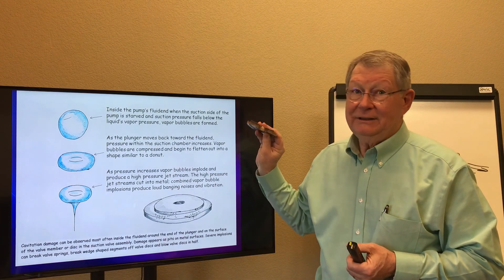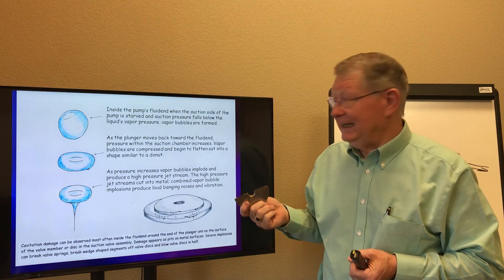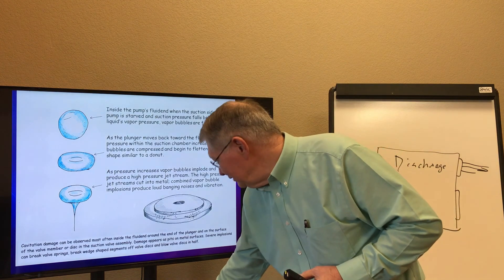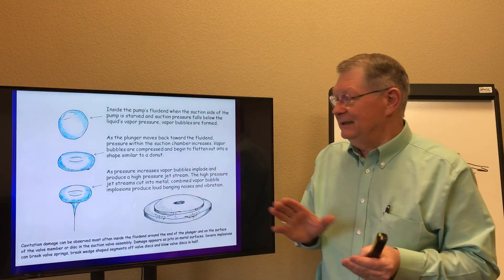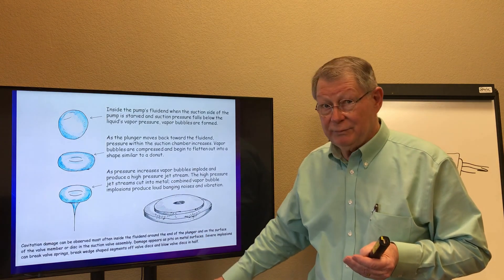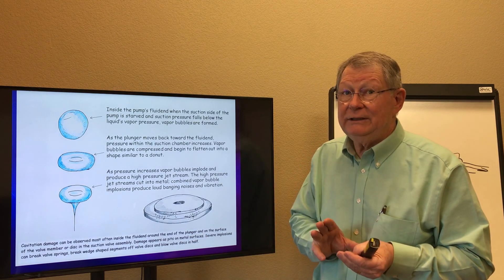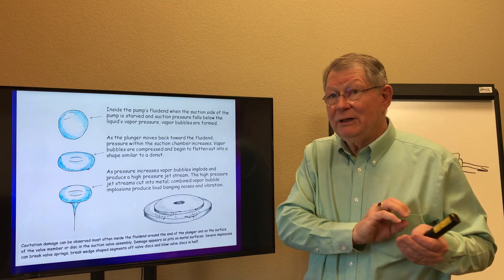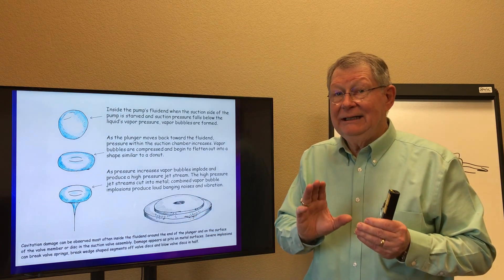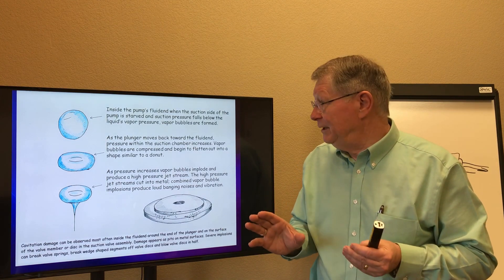Here we can see a valve disc — this is an actual valve disc that the illustration was taken from — with significant damage along it. These pockets of damage were caused by the pinpoint high-pressure stream from imploding cavitation bubbles. A valve disc can even be blown in half by cavitation. All this vibration is not only destroying pump valves and elements of the fluid end, but it's moving back into the power end and can eventually destroy the entire pump.